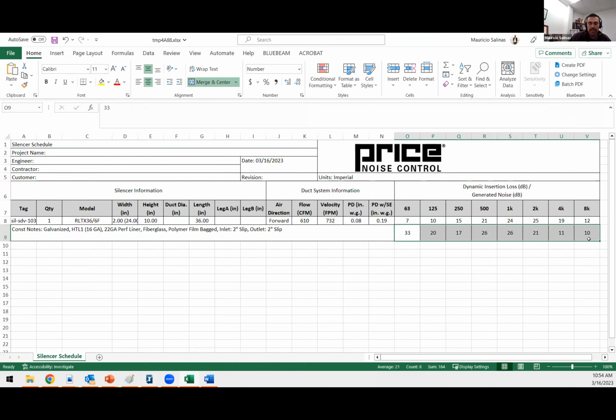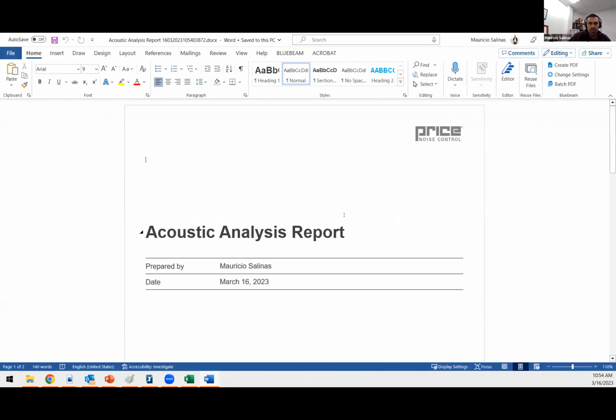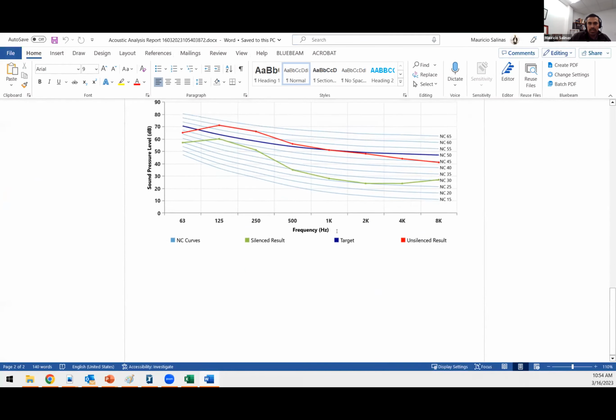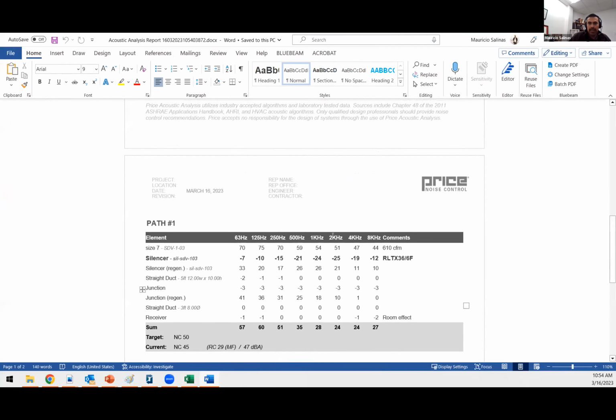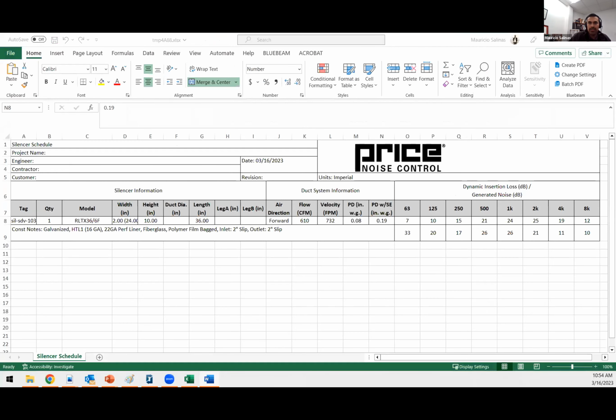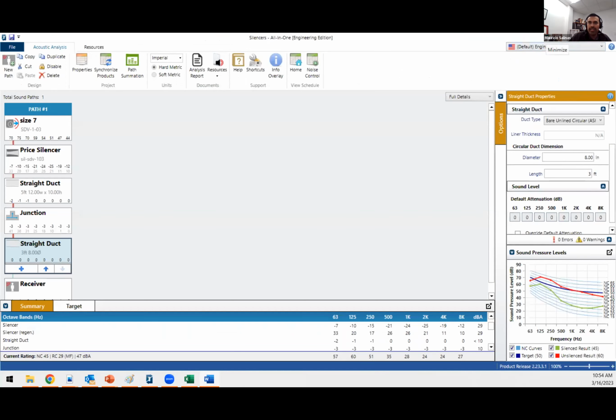You need this to be the max because I could add to the overall level. This is the minimum insertion loss, the sound you're taking out of the single duct valve. This is your installed pressure drop. These are your dimensions. And this is the report that will back up your selections. And that's how easy it is to use a very exciting software that's not boring at all.